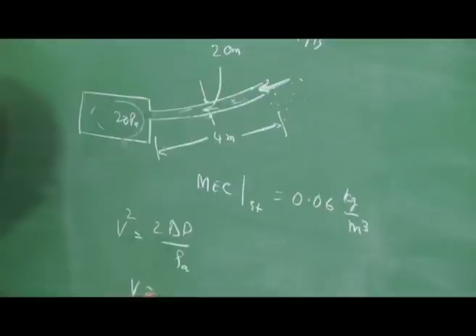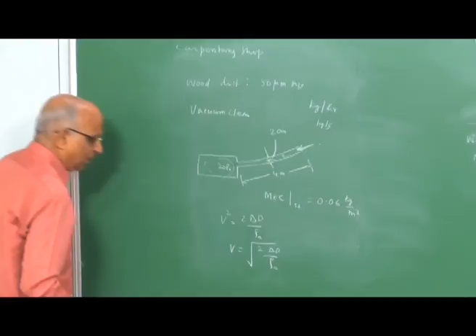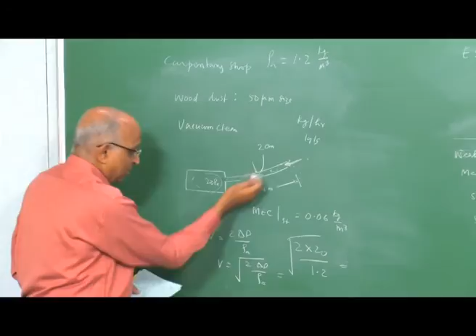V squared by 2 is equal to delta p by rho, and therefore V is equal to the square root of 2 into delta p by ambient density of air. I take the value of delta p as 20 Pascal, that is 20 newtons per meter square, so 2 into 20. The density of air at atmospheric pressure and temperature is around 1.2 kilogram per meter cube, and therefore the velocity with which the air is flowing in this duct is 5.77 meters per second.